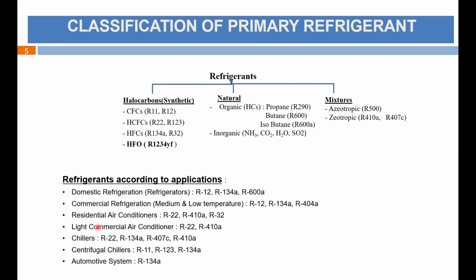So these are very common usage or application of refrigerant depending on the application. Domestic refrigerator, R12 is already phased out, so we generally use R134A, R600A. Commercial refrigeration, R134A, R404A. These are used for the refrigeration purpose. Residential, we are still continuing with R22. R410A, R32 is a substitute. Light commercial air conditioning, mainly ducted kind of system, package kind of system, we are using R410A, R22. Chillers, in Indian scenario, we are using R134A, R410A, R407C. Centrifugal chiller, R123, R134A. Automotive air conditioning, R134A. These are all in Indian context.